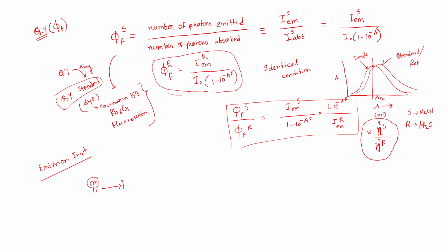So there is one monochromator unit, which is known as the excitation monochromator. I will not write much. Here will be your sample, right? This is your sample. Here you don't need any reference, any blank solution, because the fluorescence will only come from your fluorescence sample or the fluorophores. The solvent itself is not emitting. At 90 degrees to the source, your emission monochromator and your detector will be there, which is generally a PMT detector or something else.